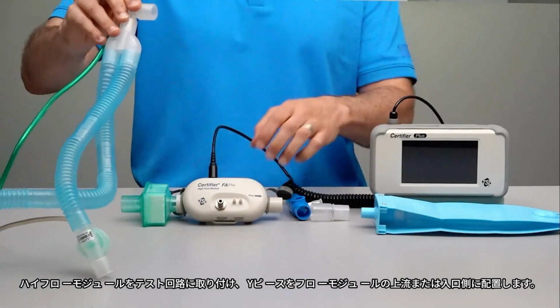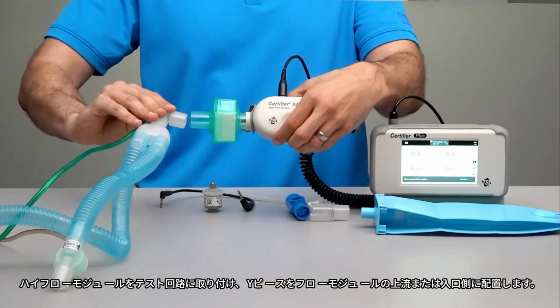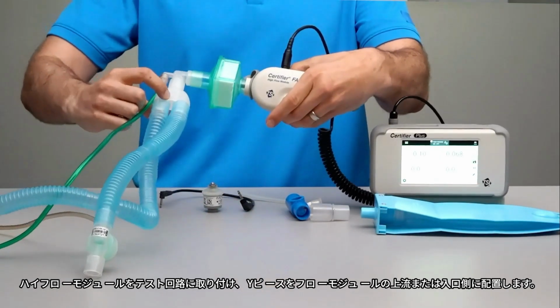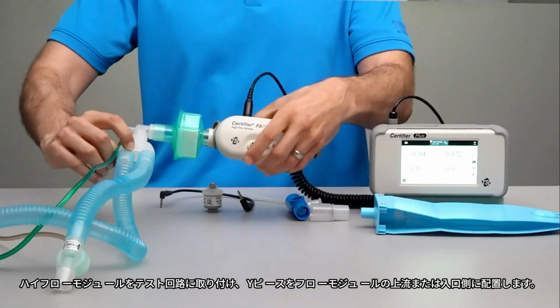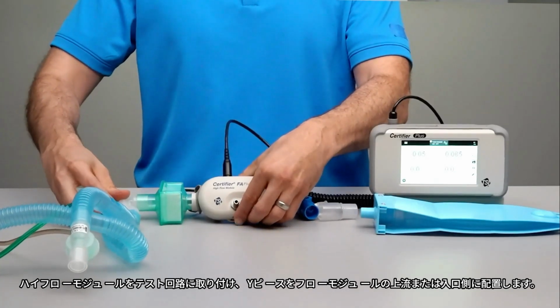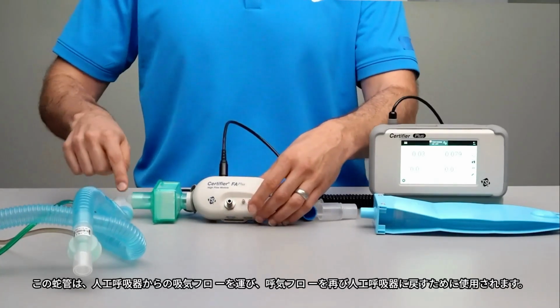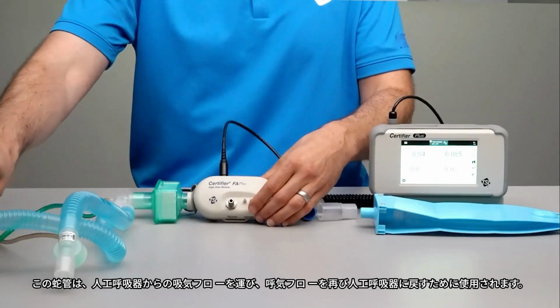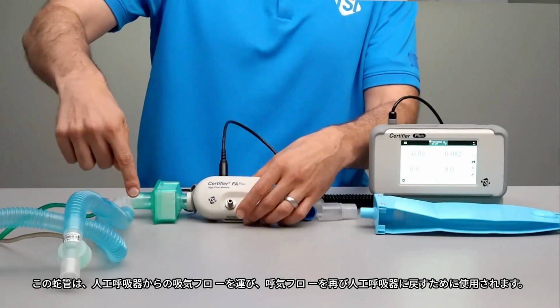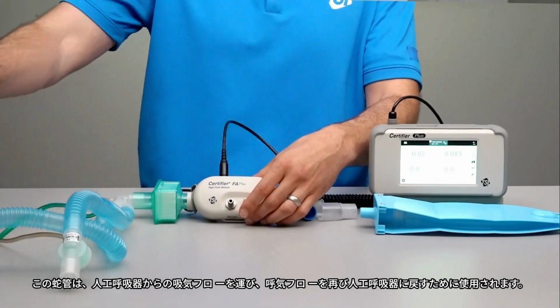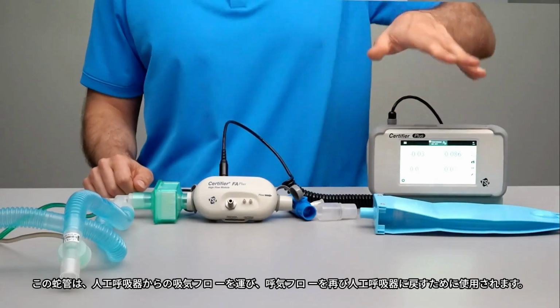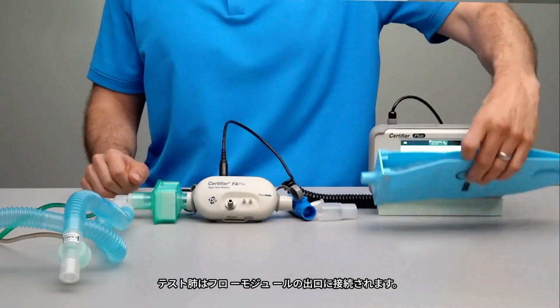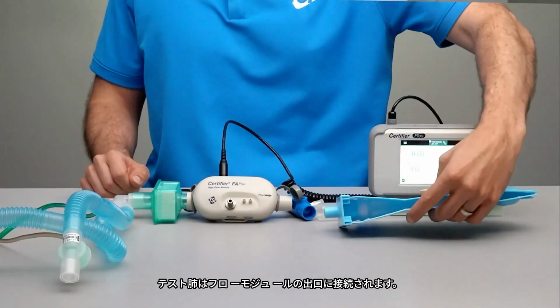Install the high flow module into the test circuit with the Y fitting upstream or on the inlet side of the flow module. This corrugated tubing is used to carry inspiratory and expiratory flows from the ventilator and then back to the ventilator. A test lung will be connected to the outlet of the flow module.